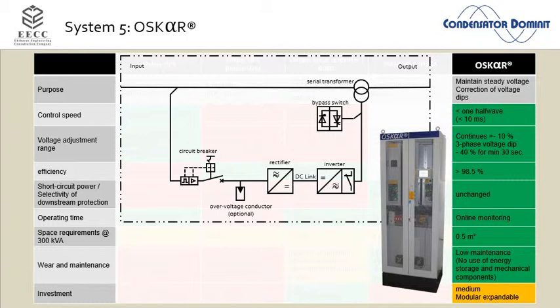Then when we originally wrote the first document where we said we want to develop such a product, how fast must it be? How fast must the voltage dip correction equipment be? How fast must an active voltage conditioner be? Then we decided for ourselves 5 milliseconds. So we wrote into the documents that the goal is we must be faster than 5 milliseconds. Forget it. Nowadays, 5 milliseconds in power electronics is eternity. The young engineers your age look at me and say, boss, hey, 5 milliseconds? I'm talking nanoseconds here. I'm in the gigahertz range, microseconds, but not milliseconds. Forget it. And that's what we did.